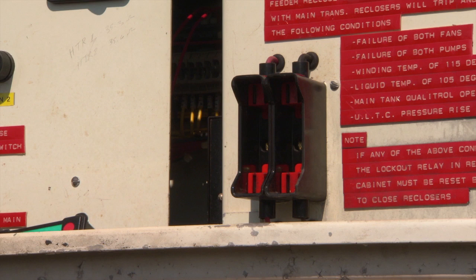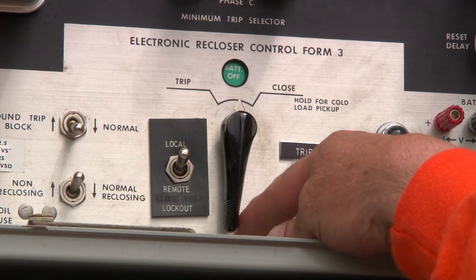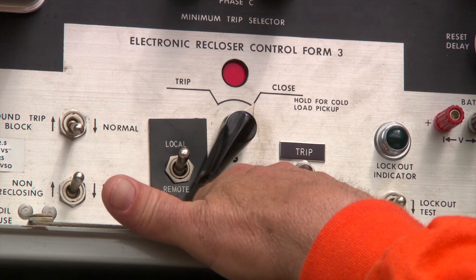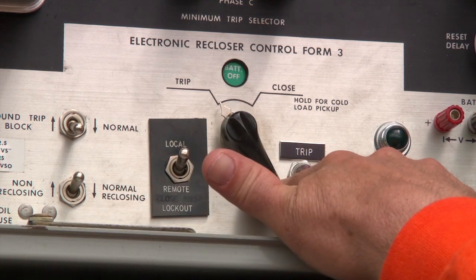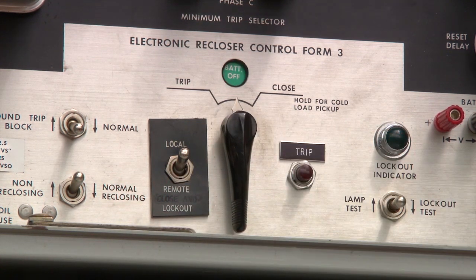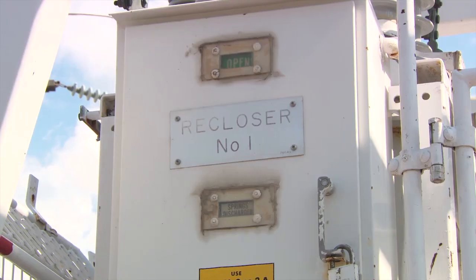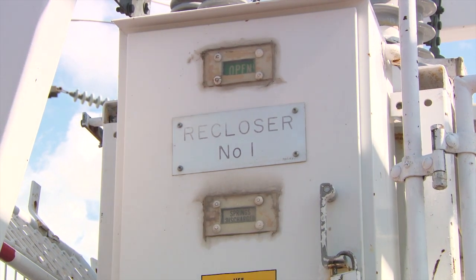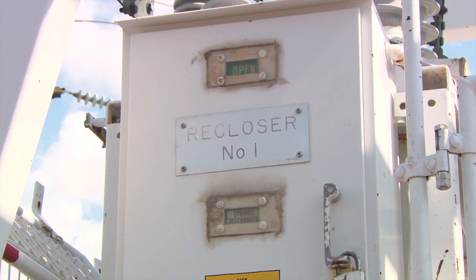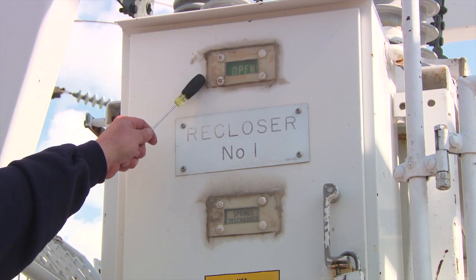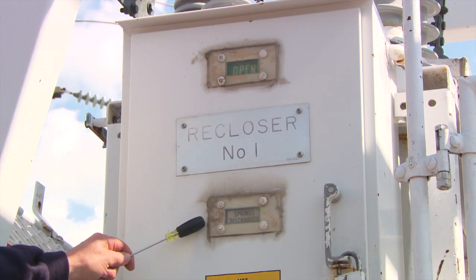Check that the F21 and F22 OCR AC supply fuses are removed. Perform the close trip operation on the F1 recloser. Set the close trip selector switch to the close position and then to the trip position. Verify that the F1 recloser tripped and the closing springs did not recharge. This confirms that there is no chance of the recloser accidentally closing during cable installation.